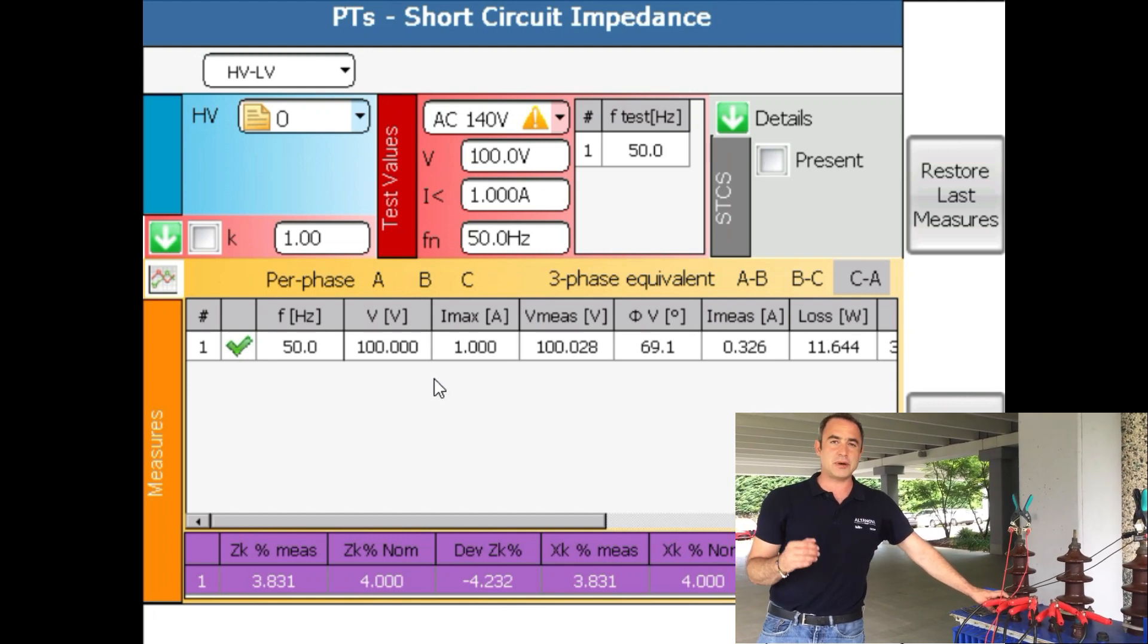Of course what you can do now to make this test a little bit more interesting is to change these positions of the tap changer and do the same test on different positions, which would give you a much better overview of the whole state of the transformer. But if you get more or less good results for this position of tap changer then you don't need to repeat anything.